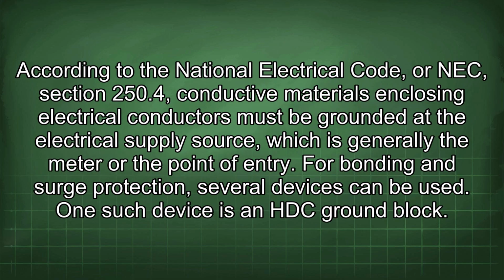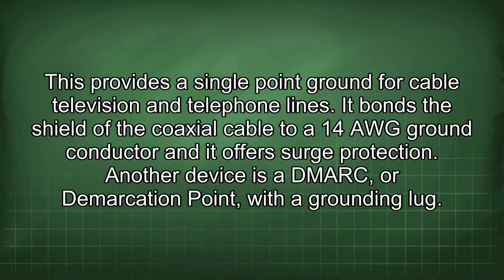According to the National Electrical Code, or NEC, Section 250.4, conductive materials enclosing electrical conductors must be grounded at the electrical supply source, which is generally the meter or the point of entry. For bonding and surge protection, several devices can be used. One such device is an HDC ground block. This provides a single-point ground for cable television and telephone lines. It bonds the shield of the coaxial cable to a 14 AWG ground conductor and it offers surge protection.